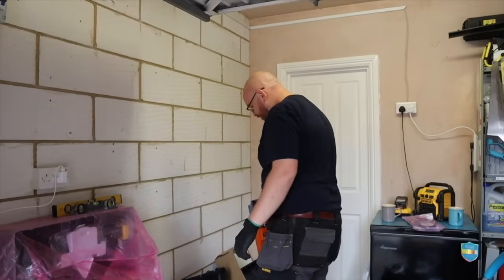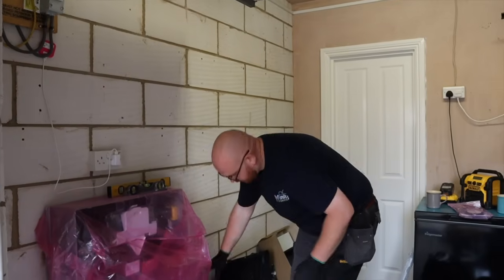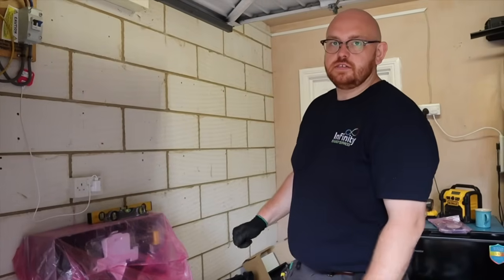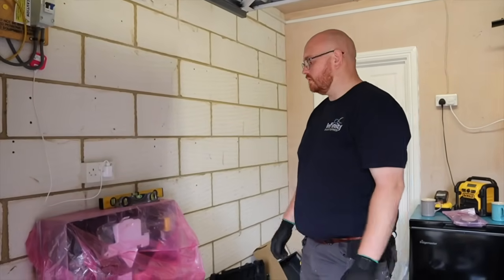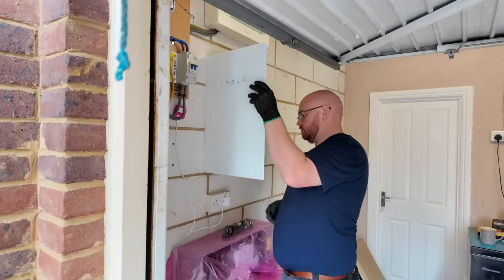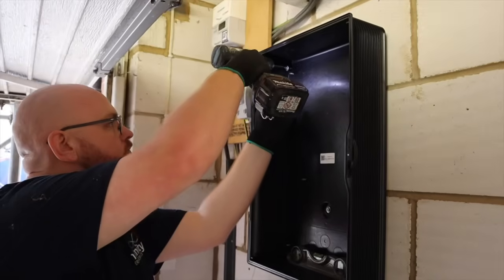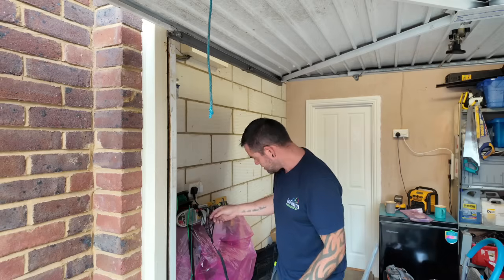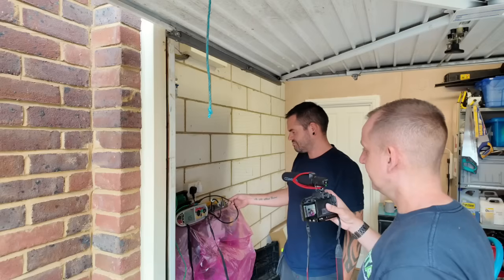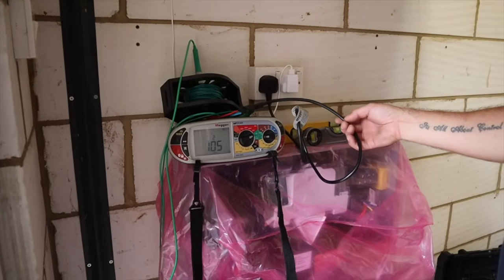And that's what the earth spike is for. If you lose your earth in the event of a power cut — when they're digging up the road and cutting your supply off — you'll have no earth connected. So we need to put in a solitary earth and get an earth reading. Other manufacturers require you to install a separate consumer unit for essential supplies, but because of the way this has been set up, this will back up your whole electrical installation, not just your lights and a socket. The earth spike reading came back at 105 ohms, which is well under the required 200 ohms — perfect.